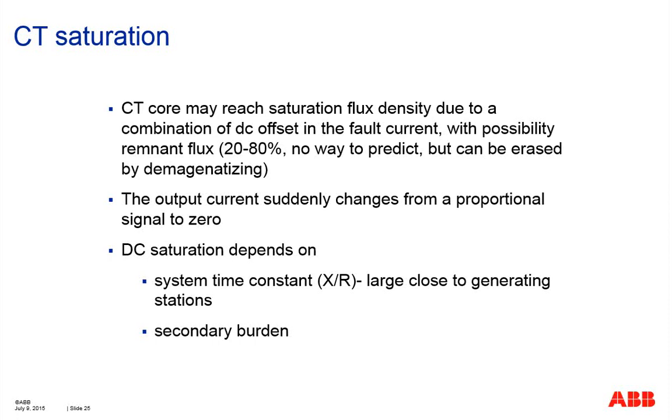So typically, as a protection engineer, when you calculate relay differential settings, you would design from a conservative aspect that you assume the remnant flux actually goes against you. That actually reduces the size of your core, making your CT much easier to saturate. So basically, you account for that using your differential setting, your slopes.